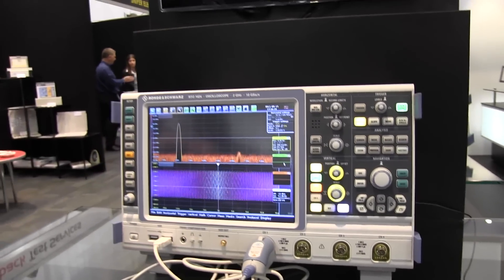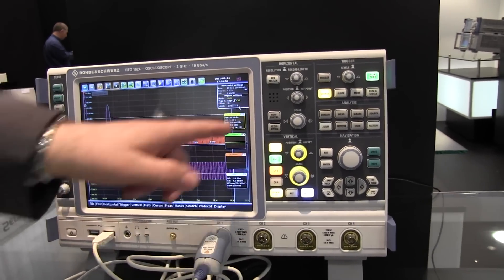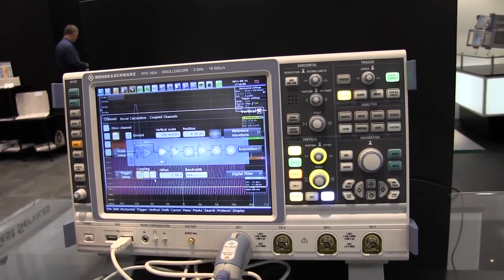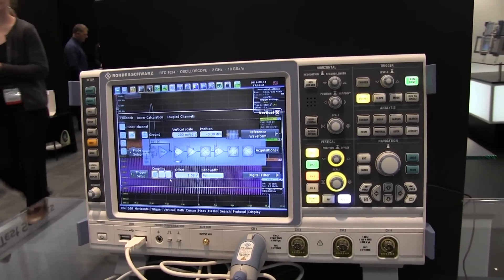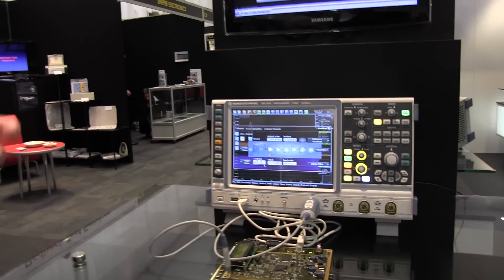What OS does that run, do you know? It is running... Windows 7 embedded. And how long does it take to boot? Three to five minutes. It's not as quick as you might want. But at the end of the day, to do this sort of display processing, to have the data interfaces, the printer drivers and all the other ins and outs you need in a modern instrument, you either have to write it yourself, use Linux — which is what we do in the generators — or you end up with the smallest possible version of Windows you can run. And that's what that is.